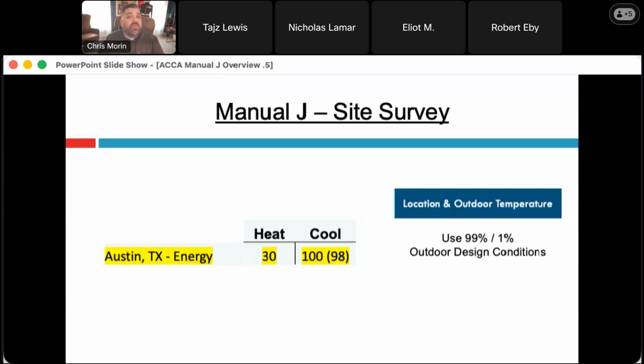So 98 degrees represents the 99% design temperature, meaning 99% of the time it's 98 degrees in Austin or less. Only 1% of the year, when you add up all the hours it's over 98, does it add up to 1% of the year. So 3.65 days when you add up all the hours. Now, of course, that could be split over months, right? Because it's only, 99 or 100 or 110 for an hour, right? So that's 1 hour. It doesn't measure how extreme that is above it. It's only the number of hours above it.